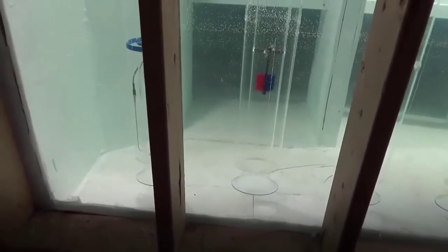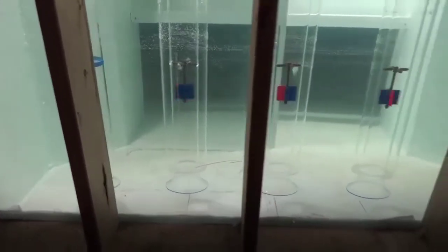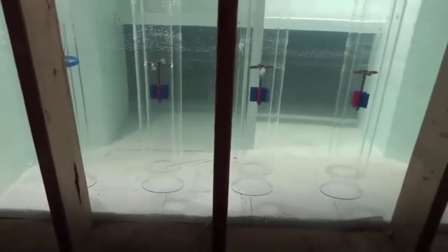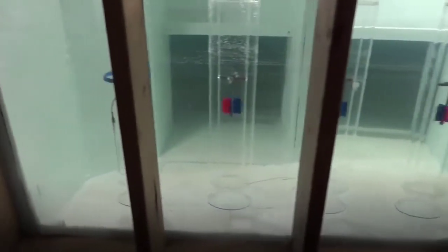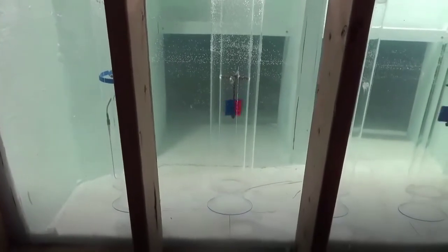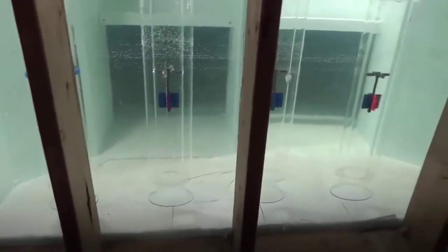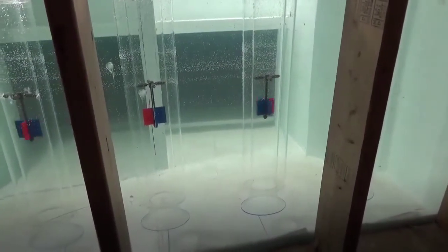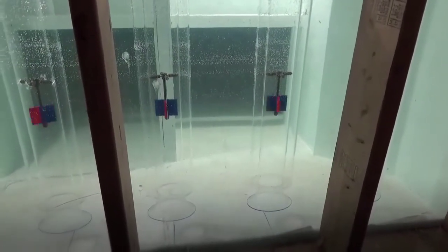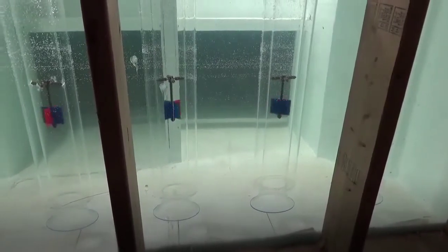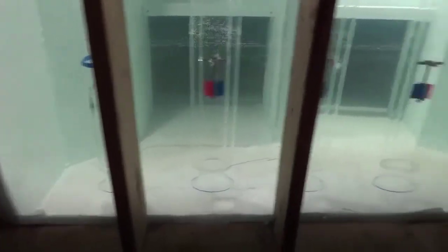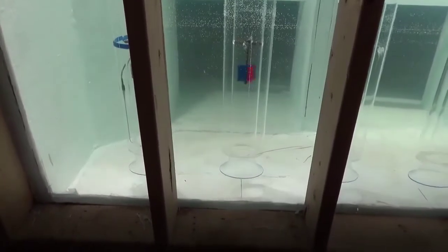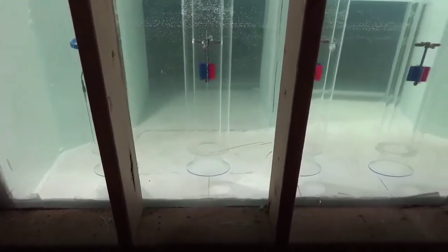The Hydraulic Institute will allow 5, and we try to be lower than that when possible. So we're double what's normally allowable. This can cause these pumps to really react in ways you're not anticipating. So we understand that one pump, particularly the last pump in the series, in the far end of the discharge header, has vibration. The fact that there's very high pre-swirl could be contributing to that. Pre-swirl is in different directions. That may be having an impact on it. And the vortex activity as well.